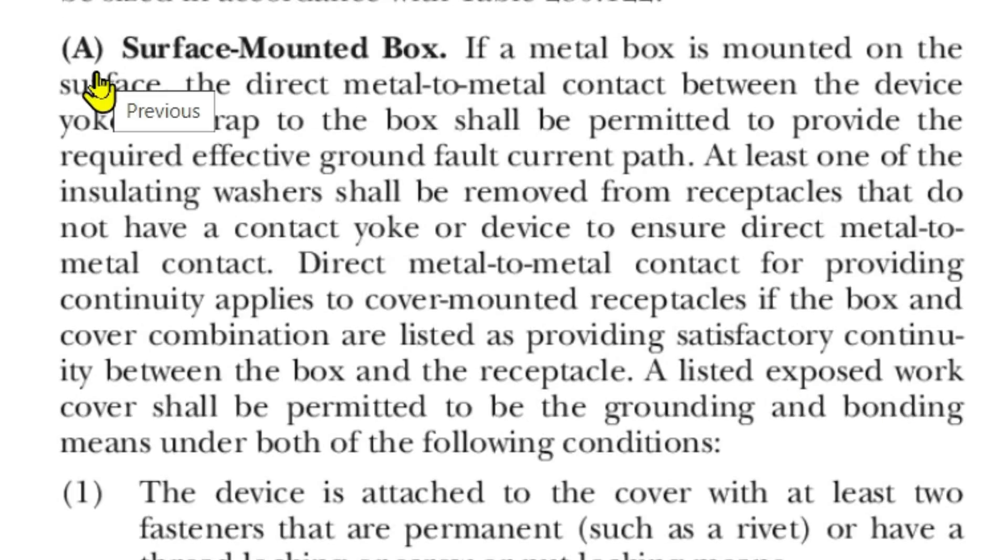So here's A right here - surface mounted box. If a metal box is mounted on the surface, the direct metal to metal contact between the device yoke or strap to the box shall be permitted to provide the required effective ground fault current path. At least one of the insulating washers shall be removed from receptacles that do not have a contact yoke or device to ensure direct metal to metal contact.